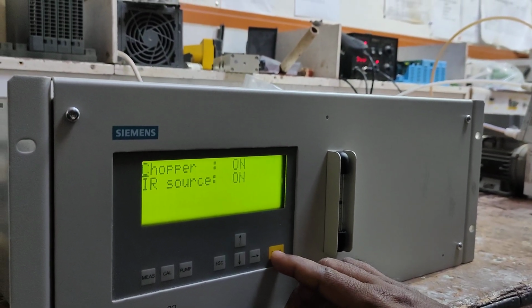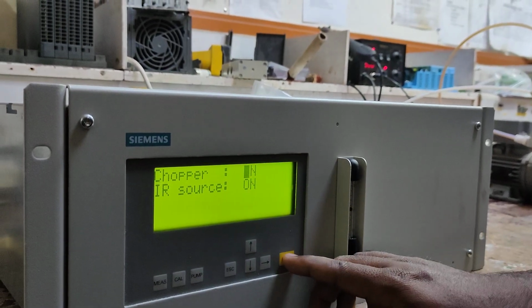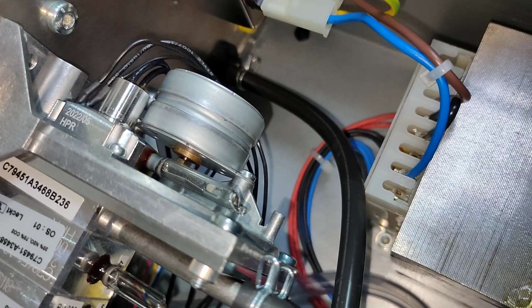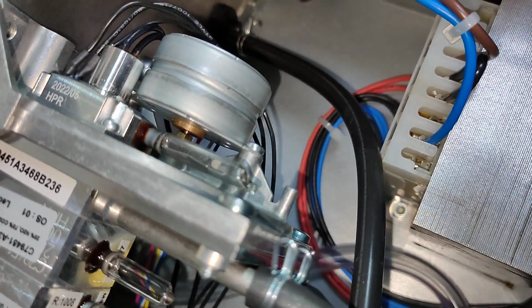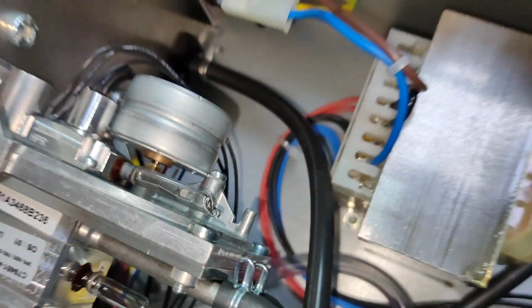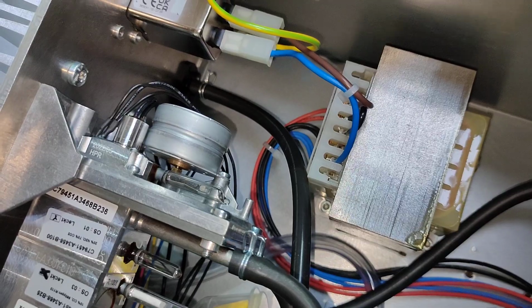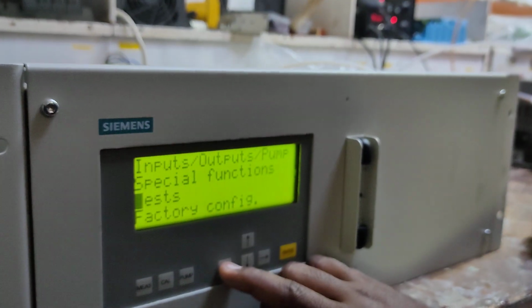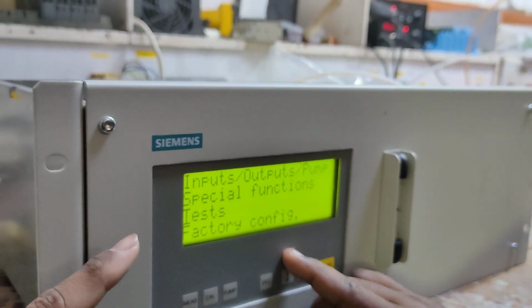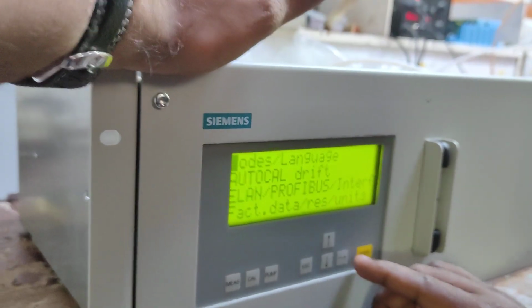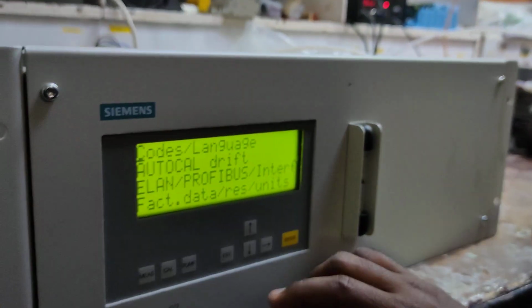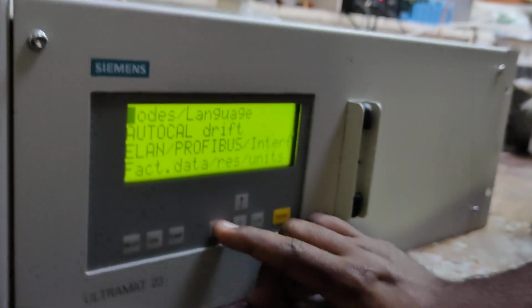Chopper motor, IR source. You can see whether the chopper motor is on or not. You can switch it off, and you can check the chopper motor is off. Now I will switch it on. Okay, it is on. But normally we don't do this. If we put the IR in off condition, it means IR is off, the value will show error maybe, and it will not be measured. You will get autocal drift.